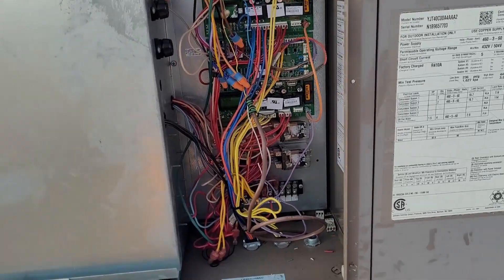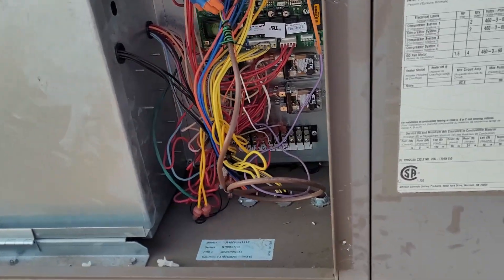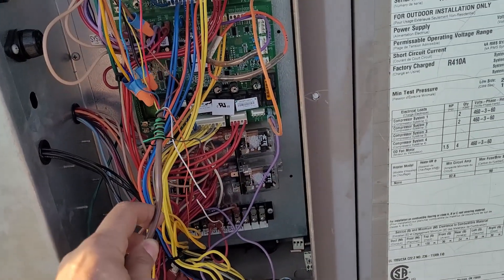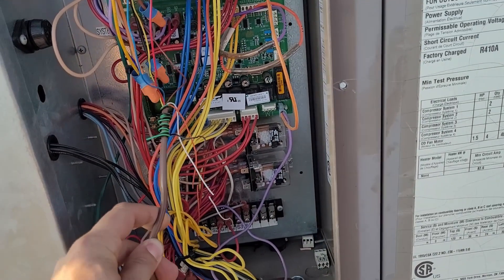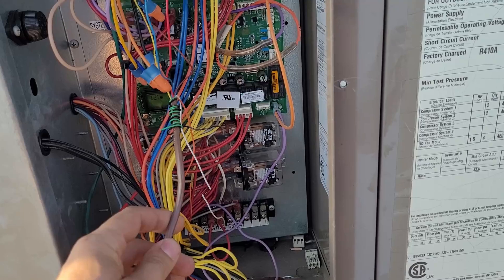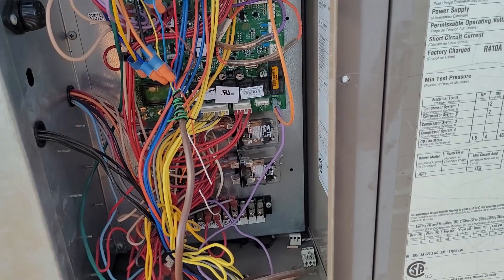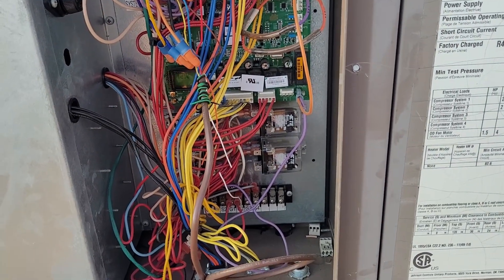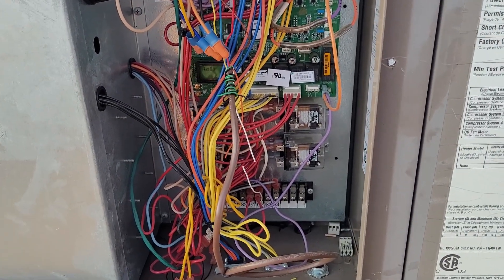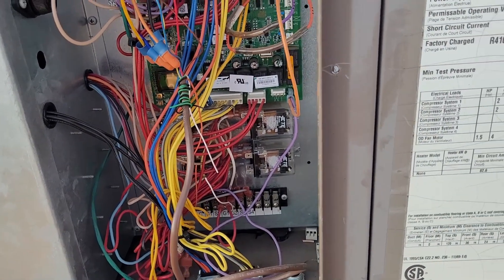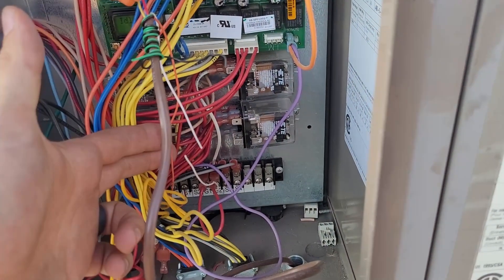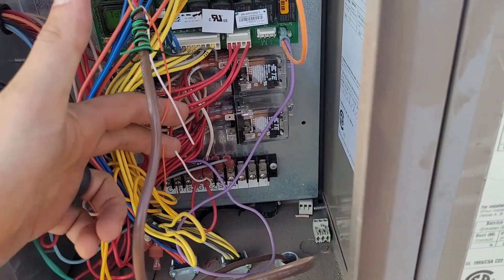So I've traced the compressor calls from the controller split in two. One leg does the liquid line solenoid valve. The other leg comes up here, and you can see I've cut the orange and the white.